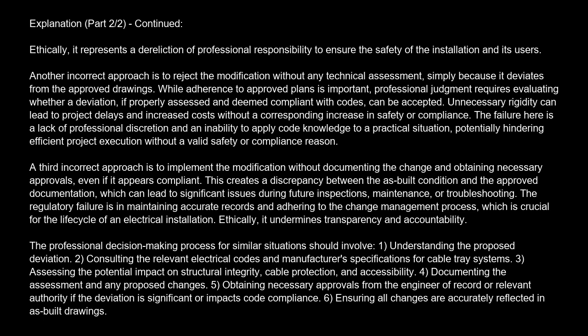The professional decision-making process for similar situations should involve: 1. Understanding the proposed deviation. 2. Consulting the relevant electrical codes and manufacturer's specifications for cable tray systems. 3. Assessing the potential impact on structural integrity, cable protection, and accessibility. 4. Documenting the assessment and any proposed changes. 5. Obtaining necessary approvals from the engineer of record or relevant authority if the deviation is significant or impacts code compliance. 6. Ensuring all changes are accurately reflected in as-built drawings.